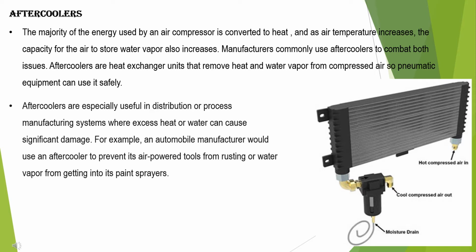Aftercoolers. The majority of the energy used by an air compressor is converted to heat, and as air temperature increases, the capacity of the air to store water vapor also increases. Manufacturers commonly use aftercoolers to combat both issues. Aftercoolers are heat exchanger units that remove heat and water vapor from compressed air so pneumatic equipment can use it safely.